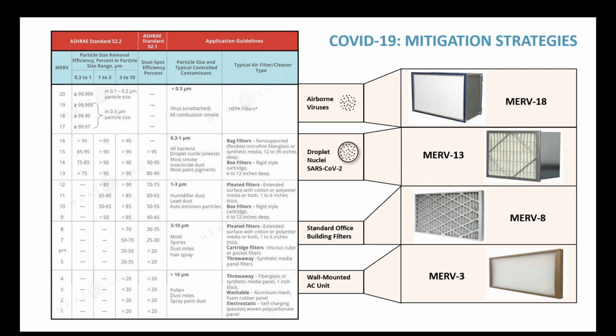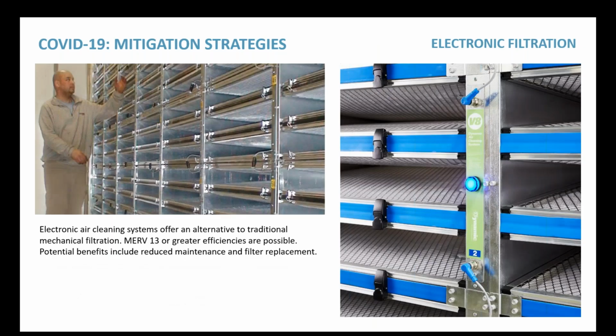Why don't we just put HEPA filters everywhere? Well, they can be quite a challenge in existing buildings to adapt your current filtration system to HEPA. And so we'll get into that a little bit more. One of the strategies we've looked at a lot for existing buildings has been electronic filtration. What electronic filtration does is it replaces your traditional mechanical filtration, but it does so in a way that allows you to achieve comparable MERV ratings, 13 or greater, that you would have with the mechanical filtration, but do so in a way that produces less pressure drop.